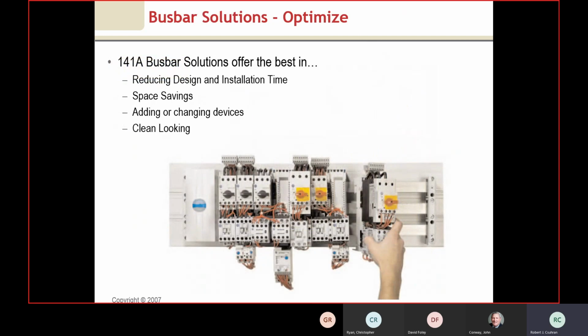Here's an idea utilizing a busbar system. This makes sense if you have anywhere between three starters or more in a system. There are a couple of real advantages. One is, as you can see, this whole unit comes wired together, so all the wiring you'd normally see between units doesn't need to take place. This snaps onto the back of the busbar—you'll notice these are the power bars—and there's a cover for it, so if you're not using all of the busbar, you have the ability to cover it.